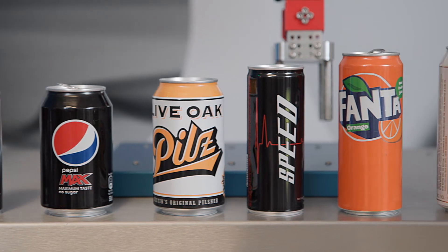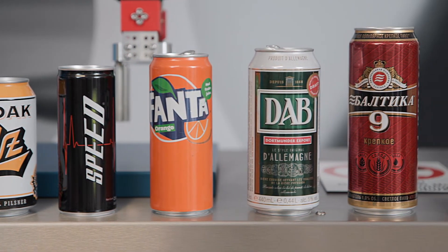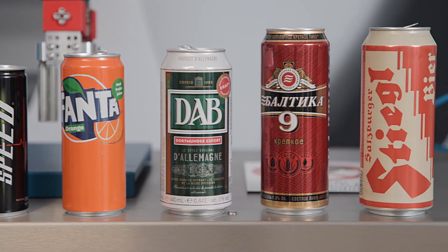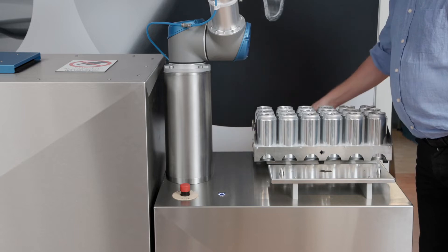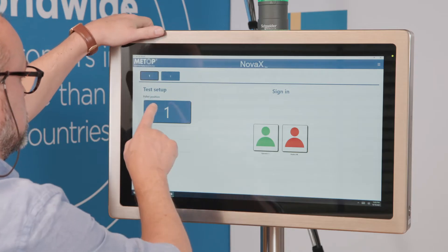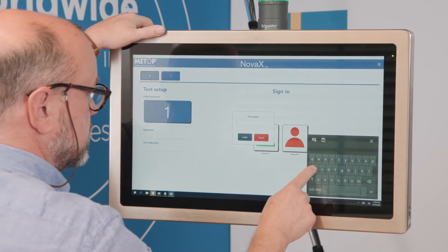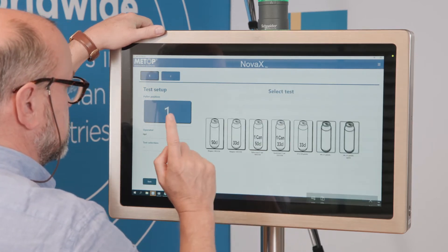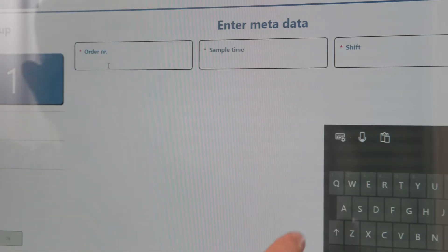All sizes of beverage cans can be measured and NovaX automatically adapts the settings. The operator selects the sample cans, puts them in the sample tray, and places the tray on the machine. The operator then logs in, creates a new test batch, and selects the sample size via the touchscreen.